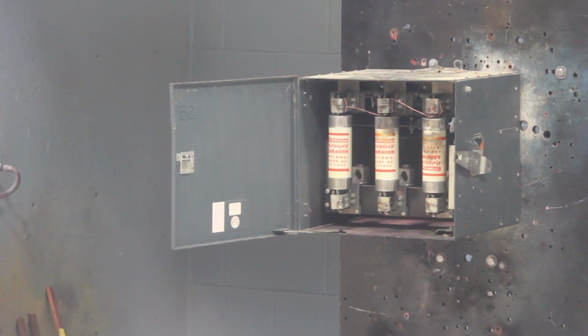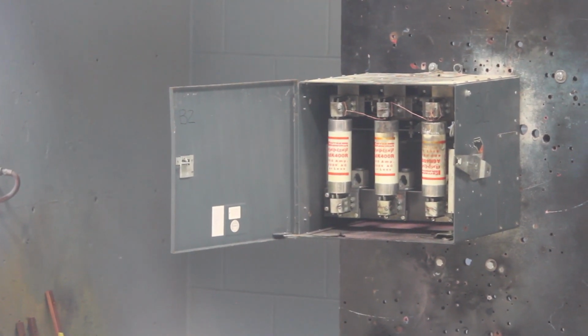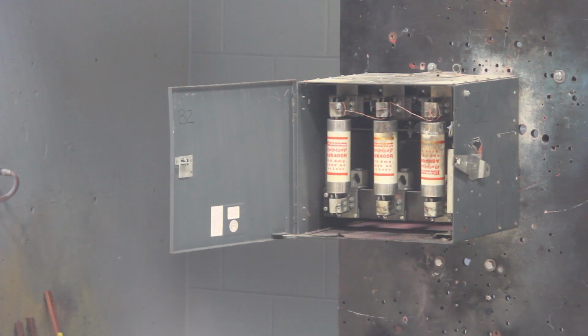In this next case, this was a bus plug. And with the bus plug, you can see the shorting wire up on the line side. And it was a little more dramatic arc flash. This was a lower current. I believe it was 208. And let's take a look at what happens. 400 amp bus plug, 400 amp fuses.